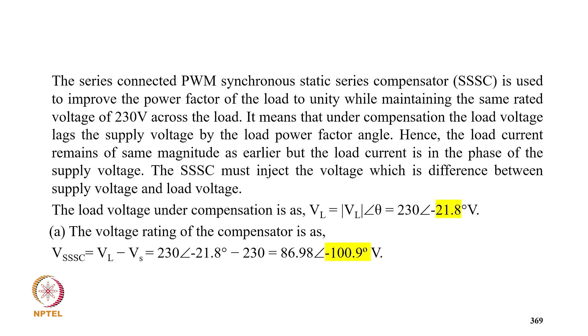The SSSC must inject the voltage which is the difference between the supply voltage and the load voltage under compensation. Load voltage under compensation VL is equal to 230 at angle minus 21.8 degree, and the voltage rating of the compensator is VSSSC equal to VL minus VS. So putting in values, it comes to 86.98 at the angle minus 100.90 volt. Since the load voltage magnitude and the load impedance are the same, the load current remains the same as without power factor correction.